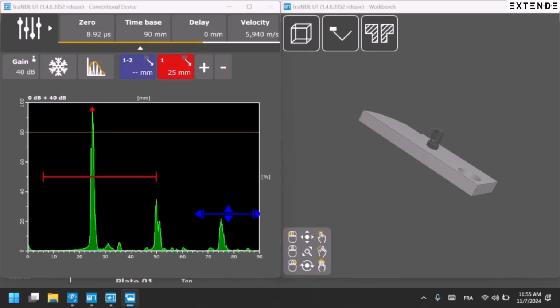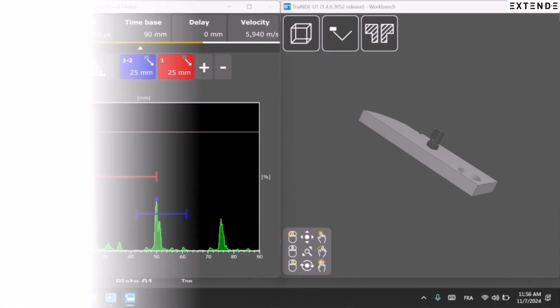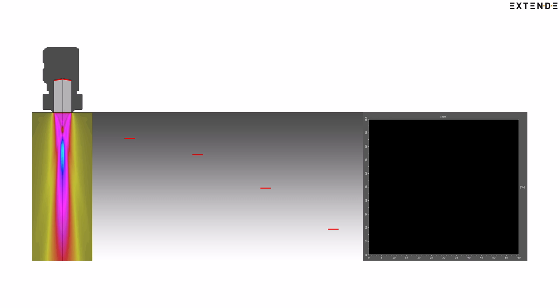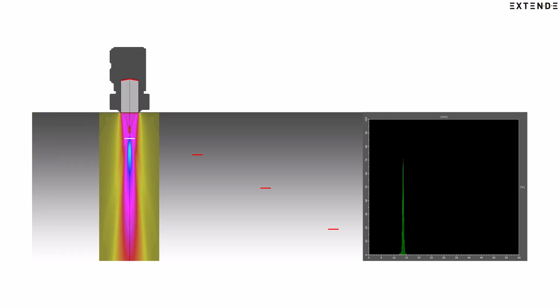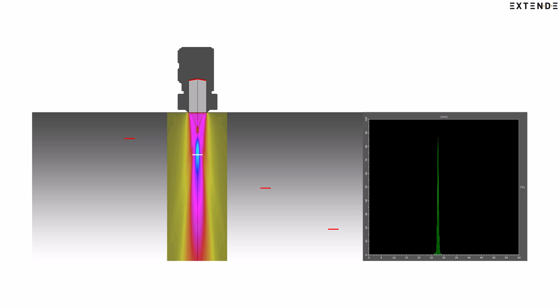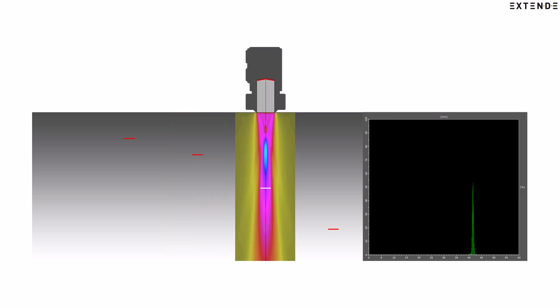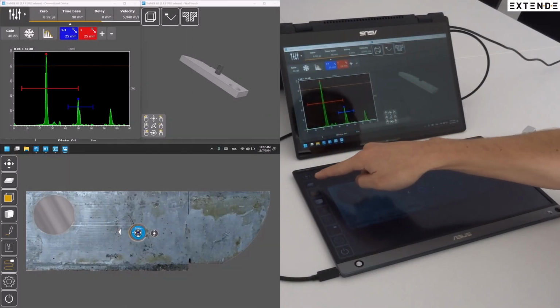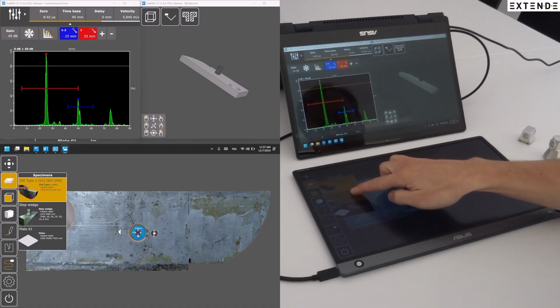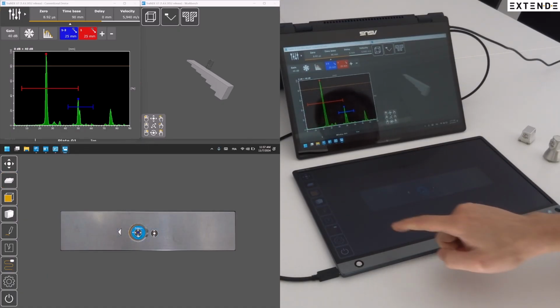The next step is to calibrate the sensitivity of the flaw detector. For this tutorial, we are using the flat bottom holes of the step wedge as reference flaws. The result of a sensitivity calibration is called a distance amplitude curve, a DAC. The DAC shows the amplitude variations of the acoustic beam transmitted by the probe within the specimen. Select the step wedge in the digital mockup. Then display the flaws.